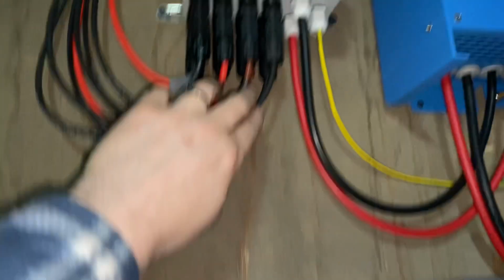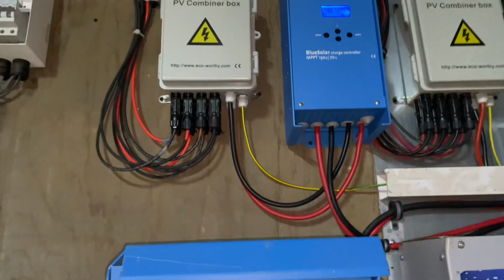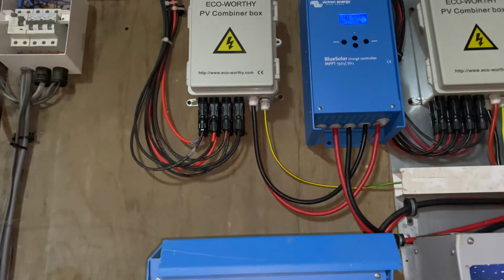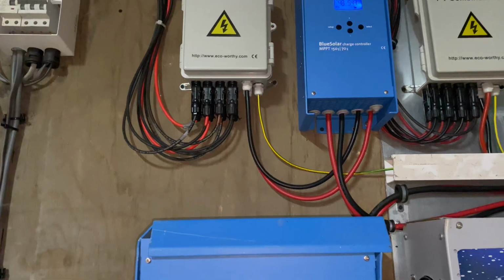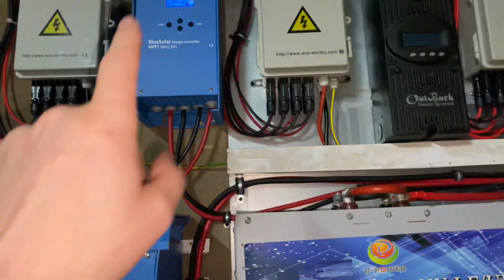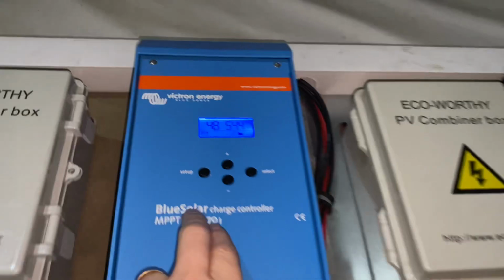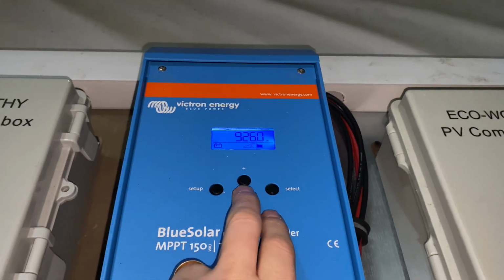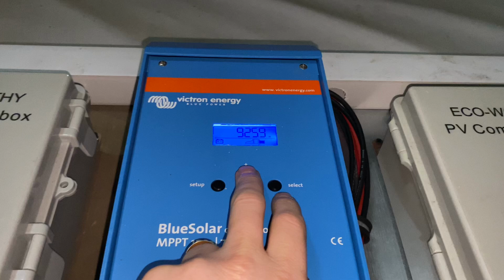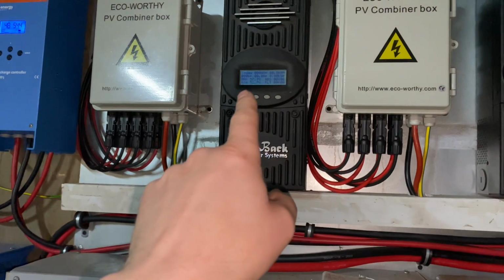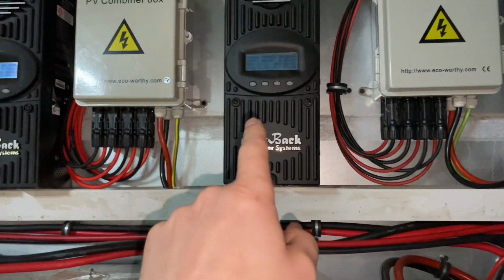So this is a combiner box. We've got 4 sets of cables coming off the roof. We've got 12 panels and they're sitting at 57 degrees, which is our angular latitude. And they are charging all these boxes, everything couples into the bus bars there. So this is our first bank of panels. The batteries are basically fully charged at 54 volts. The panels are putting 925 watts out and it's a dull, cloudy day. We've then got another 12 panels going into this bank, another 12 panels going into this bank.